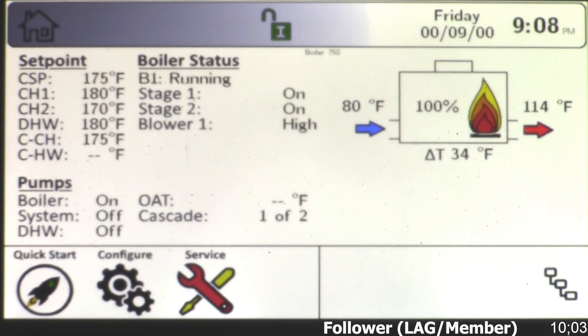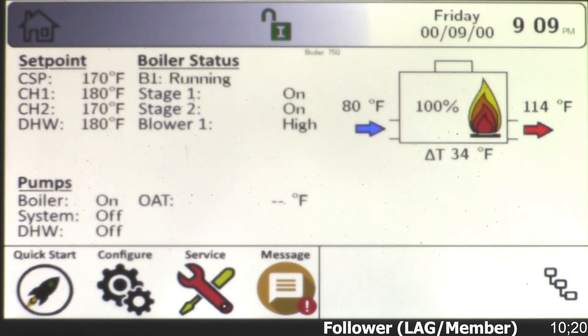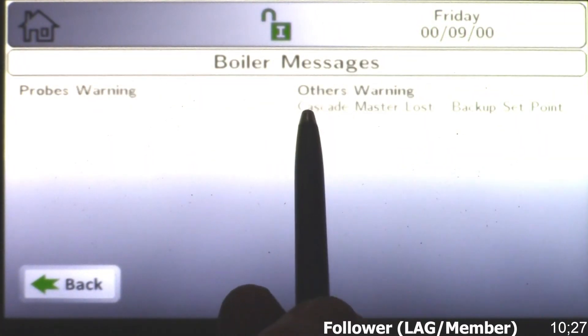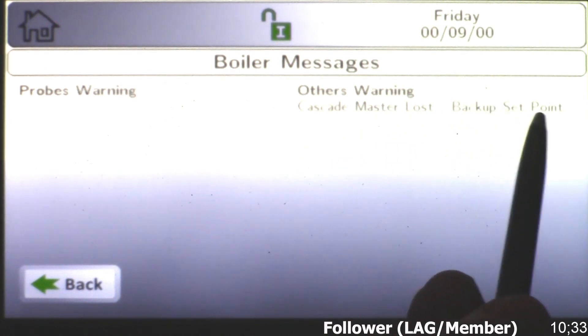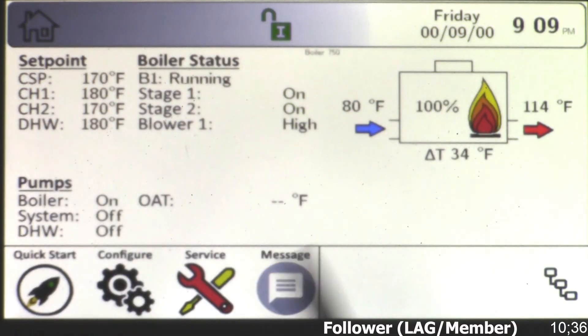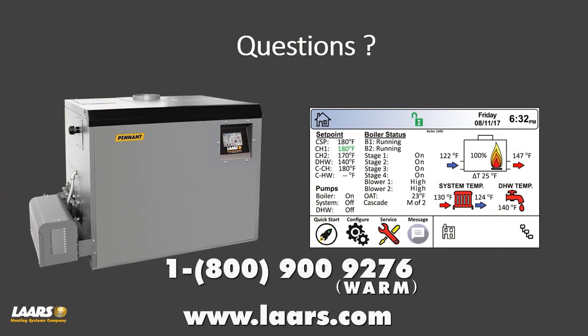Right now we're at a timeout period and still running at 100 percent in this example. Be patient — it could take 60 to 90 seconds and we'll see a message box appear. Here's our message box — the boiler is still operating. If we click on that message box, it's going to give you a warning telling you that the cascaded master was lost. We're now in backup setpoint and will stay running in backup setpoint until the leader or master boiler comes back on. For any technical questions, please contact the factory at 1-800-900-9276.